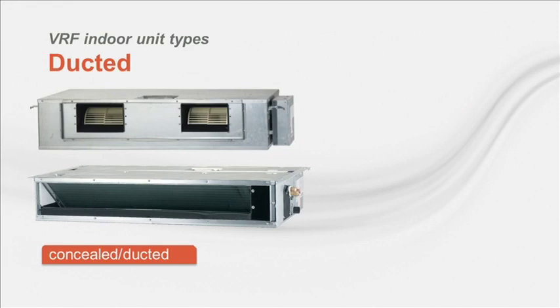Slim duct models have limited external static pressure capability and are intended for applications where supply and return ducting is minimal. Mid and high static pressure concealed units are available in larger capacities and can be installed with longer supply and return duct runs. Like the slim duct models, they are intended to be concealed in ceiling spaces. Common applications include larger conference rooms and lobby areas where 2 or more supply ducts will provide uniform air distribution and comfort, and even adjacent rooms that have common demand.